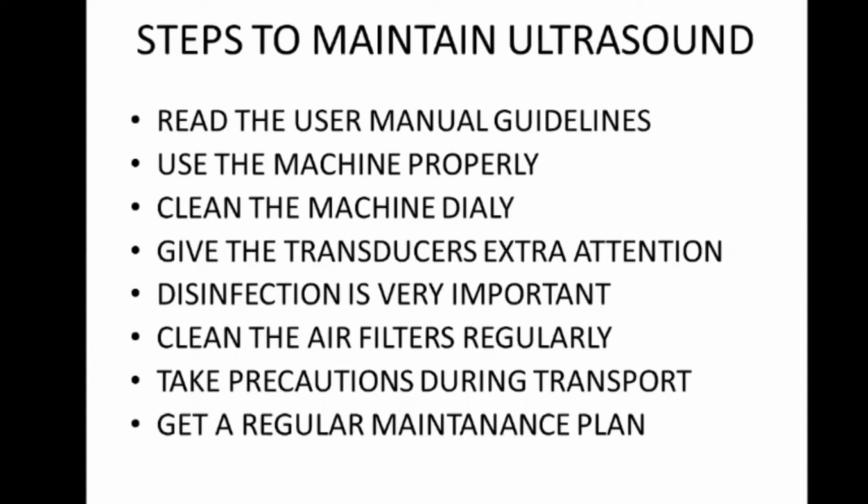You should cover the entire machine with thermocol, or you should use a sticking tape, like a glass tape. You have to cover the entire machine with the glass tape, and you have to keep the probes in each box, and then transport. You should dismantle the probes from the ultrasound, keep them in the box, and then make the transport.